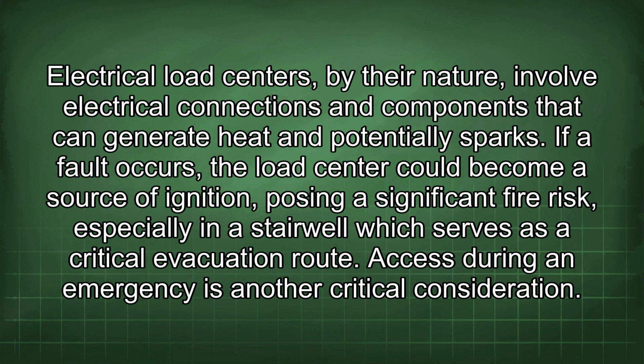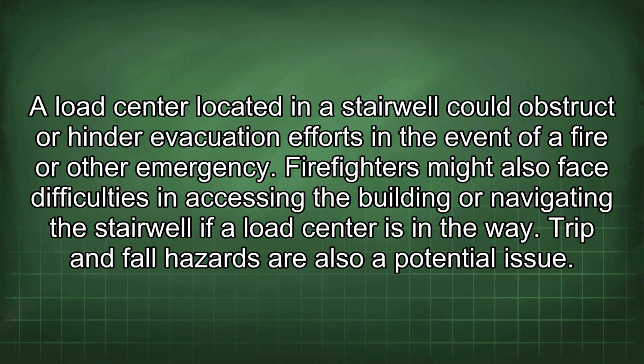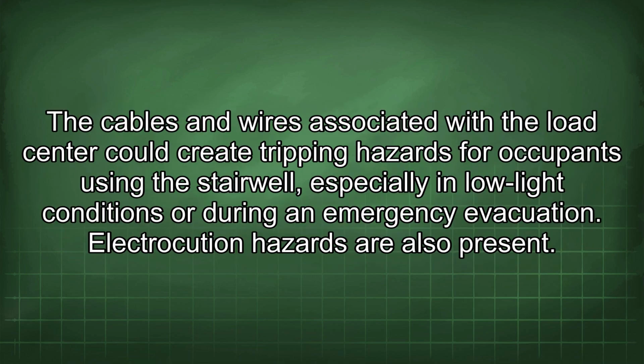Access during an emergency is another critical consideration. A load center located in a stairwell could obstruct or hinder evacuation efforts in the event of a fire or other emergency. Firefighters might also face difficulties in accessing the building or navigating the stairwell if a load center is in the way. Trip and fall hazards are also a potential issue. The cables and wires associated with the load center could create tripping hazards for occupants using the stairwell, especially in low light conditions or during an emergency evacuation.